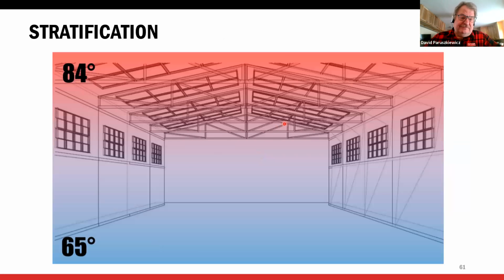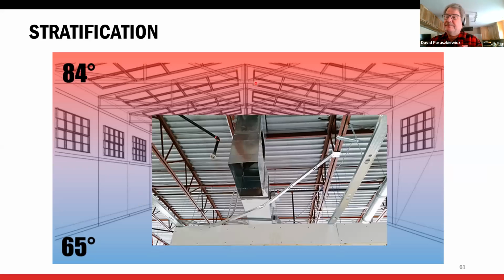Okay, something called stratification. All right, and stratification has to do with the denser cold air falling, the warmer, lighter air going up, and in a high ceiling area, we could have a drastic temperature difference in 15 feet. All right, especially if the unit's been sitting off, you go into setback at night. This is why you want to be careful of going to too big a setback. So you go into setback at night, the unit fires up in the morning, and we start to build up all this heat high up in the building, all right? Because we're stratifying. Now, what happens if your return air duct is up here? You're just using a straight drop like this, okay? And you got all this 80, 82 degree air up here because this unit's been running, trying to come back from setback.